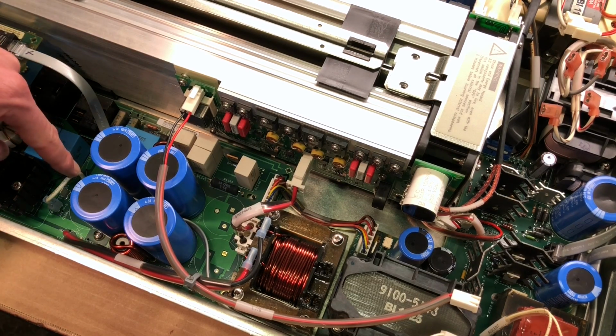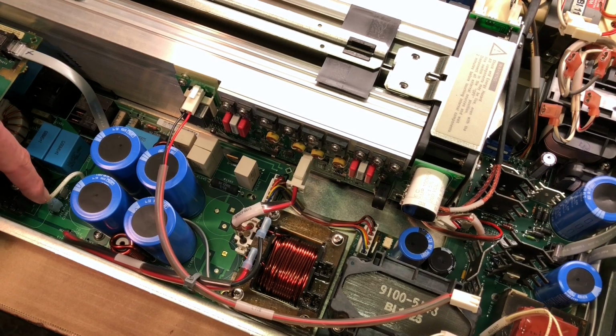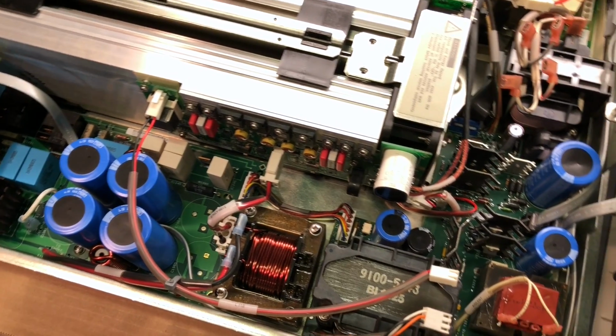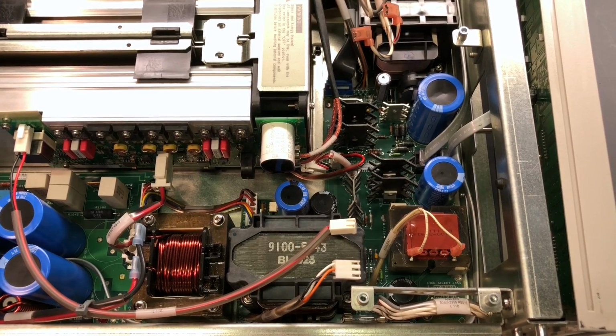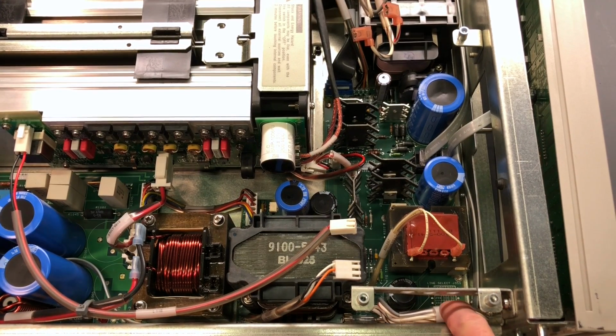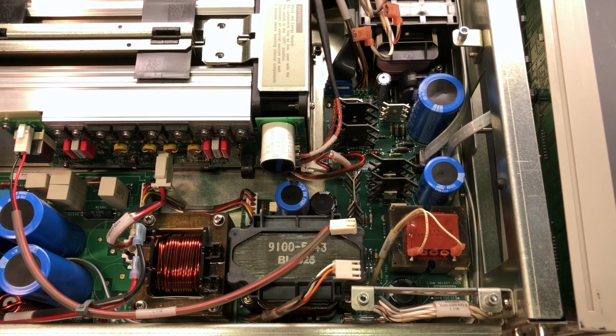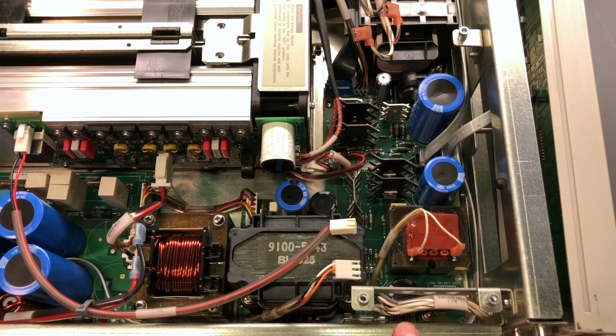One is right here, this white jumper you can see on the circuit board. This just needs to be moved over to this other terminal connection right here. So the terminal that it's on right now says 200/220, and the other position is 100/120. So that's a simple thing to move over. Now, pardon the camera movement, but get this positioned over here. So in this corner over here, right above where my finger is right there, you can see there's a little chart down on the circuit board, and there's some voltage ranges printed on that chart. And there are 3 jumpers on a terminal block right down here, right on the circuit board, down in there. So you just follow this chart that's over here and the position of those jumpers and the voltage that you want.